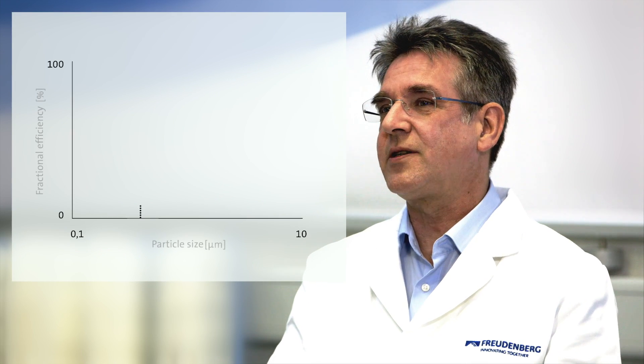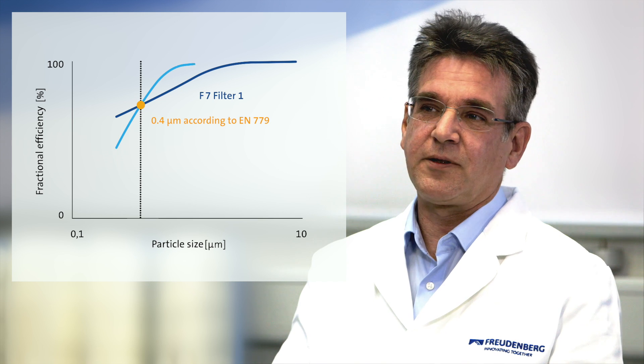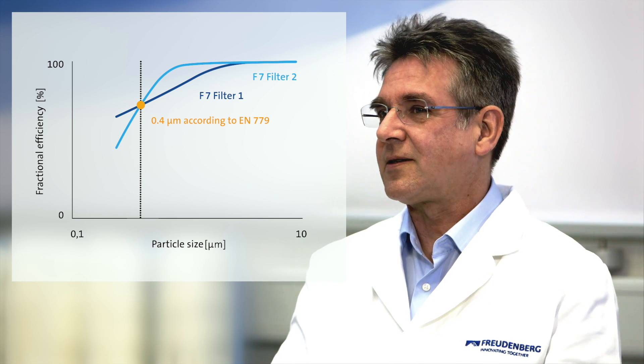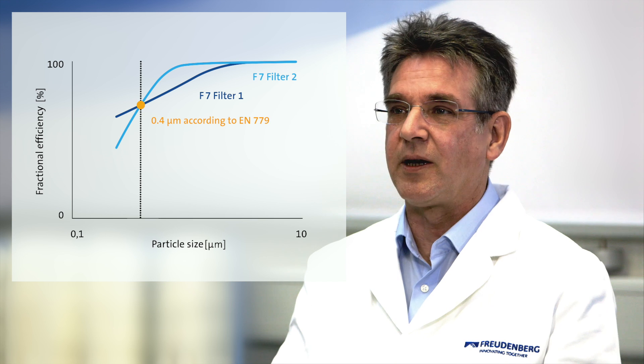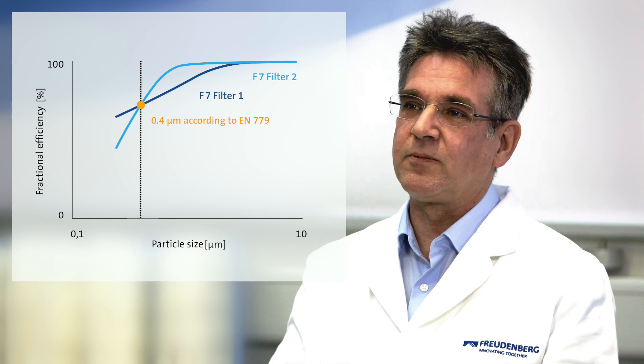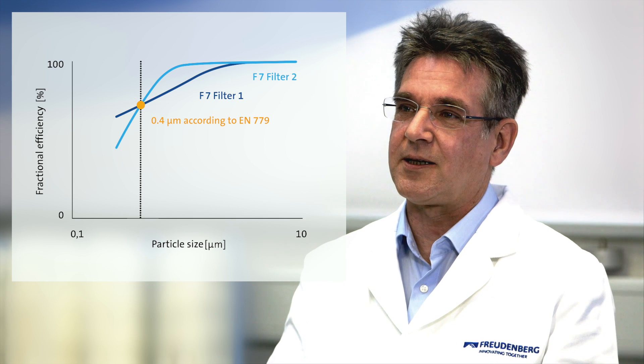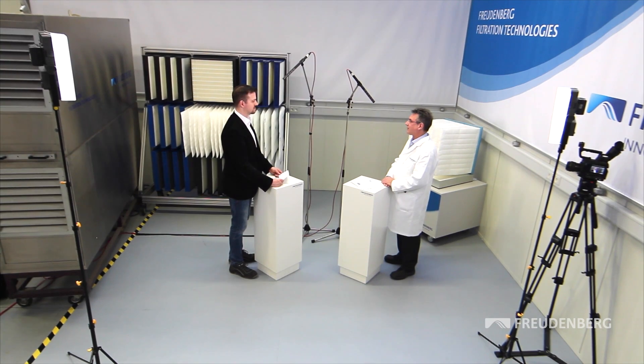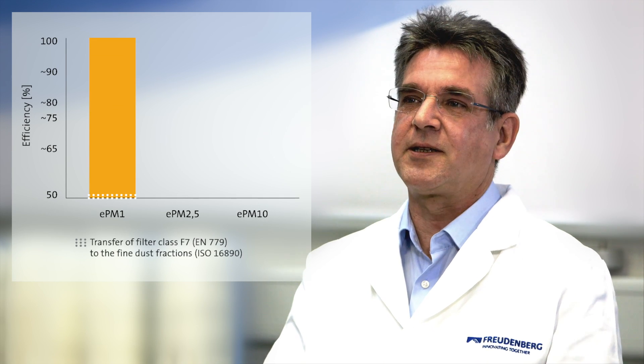How will an F7 filter be rated in the future? Unfortunately, this question cannot be answered precisely, as the new ISO standard evaluates different properties of an air filter than the current EN 779. Filters classified today as F7 — having the same efficiency for 0.4 micrometer particles — might have totally different efficiencies for other particle sizes, such as 1 micron or 10 micrometers. Consequently, these filters will also be rated differently under the new ISO standard. As a rule of thumb, most currently available F7 filters will be rated in the future as ISO EPM1 between 50 and 65%.